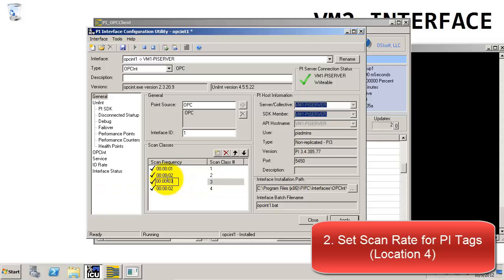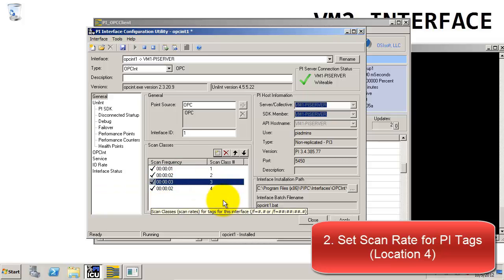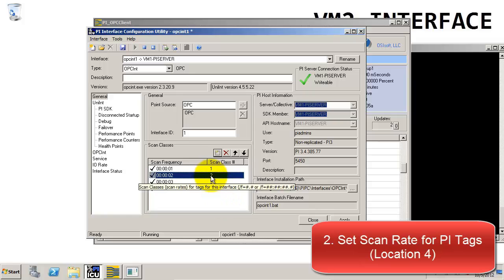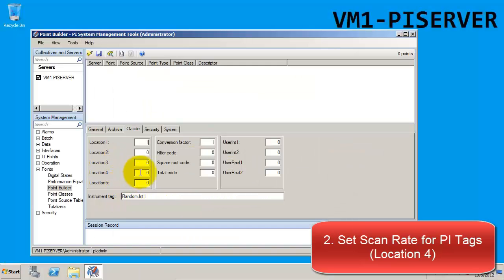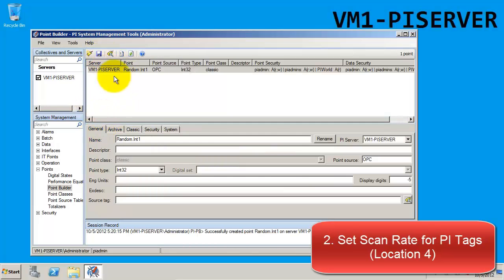For the OPC interface, scan class 1 is reserved for advise tags. So if we want to do a polled tag, we would need to choose a different scan class. How about we choose a 2-second scan frequency and stick with scan class number 2, which means we would need to pick location 4 equals 2. We'll go ahead and fill in 2 for location 4 to specify that we want to use the second scan class.